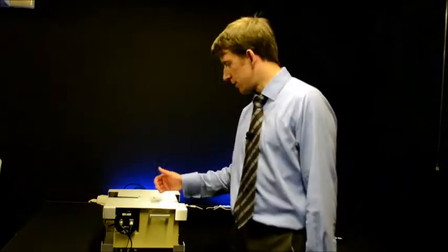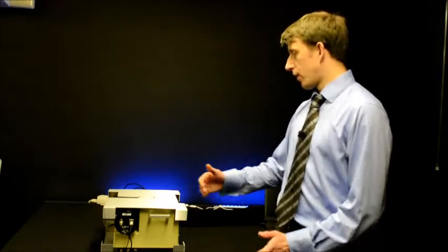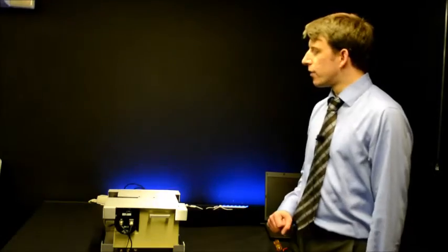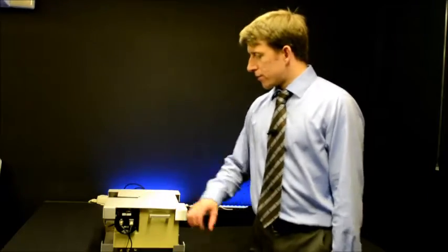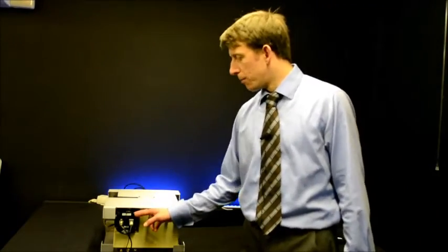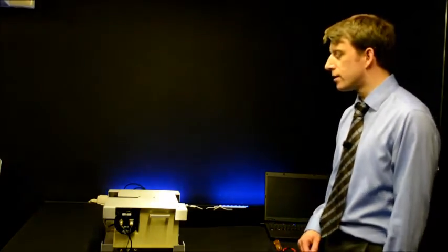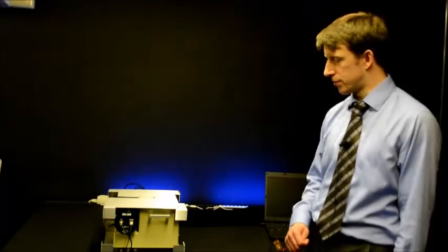The diffraction gratings fitted are mounted on kinematic mounts and are driven in tandem. The diffraction gratings are 1800 grooves per millimeter, giving the spectral range of the device around 200 to 800 nanometers. The detector used in the solar irradiance mode is the DH3 multi-alkali S20 photocathode photomultiplier, which gives very, very high sensitivity in the range 200 to around 850 nanometers.